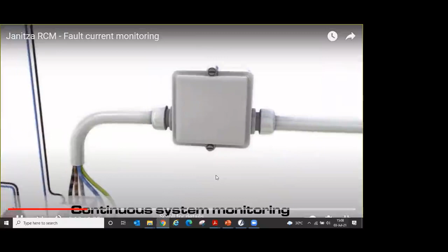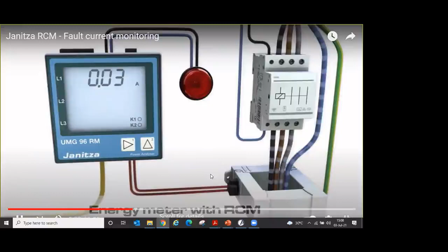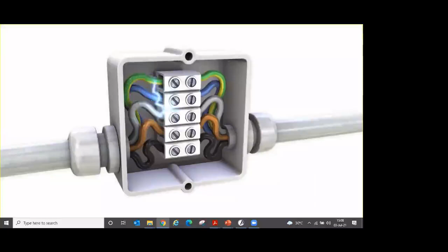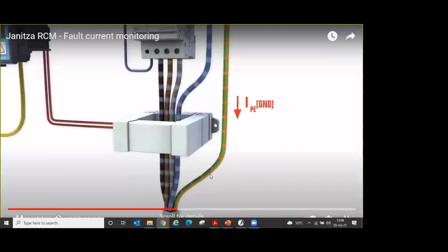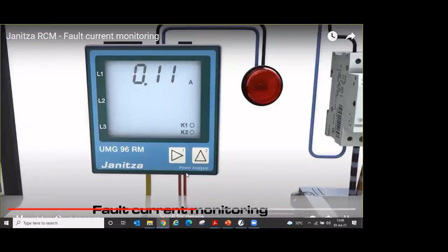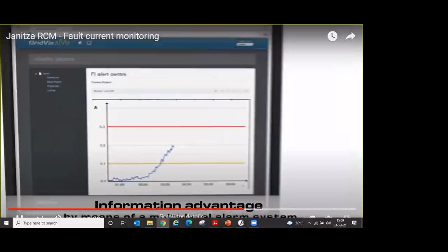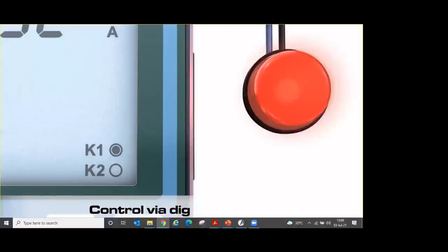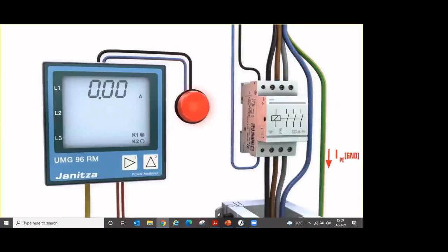An effective RCM, residual current monitoring, will detect fault currents before disruptions or plant shutdowns occur. In the measurement device UMG 96RM-E, that feature is already integrated. Utilize existing infrastructure and extend your system with residual current monitoring. That is how you will reliably identify beginning insulation faults long before they are noticed as disruption or, in extreme cases, result in fire. Because residual current monitoring is integrated in your energy management, existing communication features can be utilized. The multi-level alarm system, including traffic light function, will be conveniently operated with our visualization software GridVis. Functions like acknowledgement or escalation management can be set up. In addition to that, you can use the existing digital outputs for alarm messages. Energy management, power quality, and residual current monitoring from Janitza.